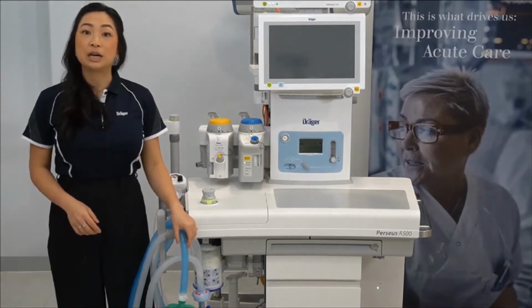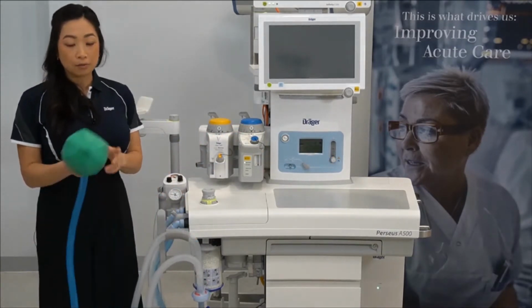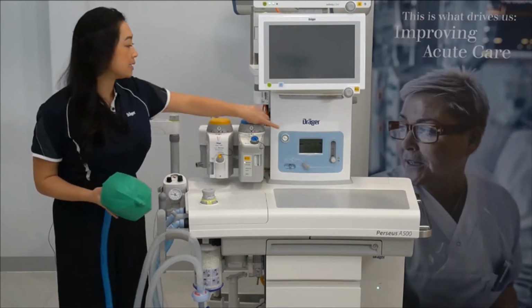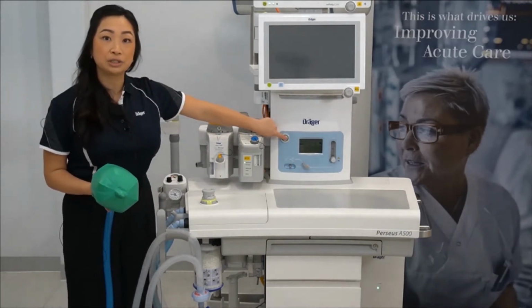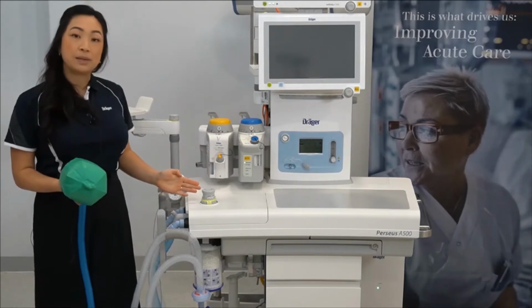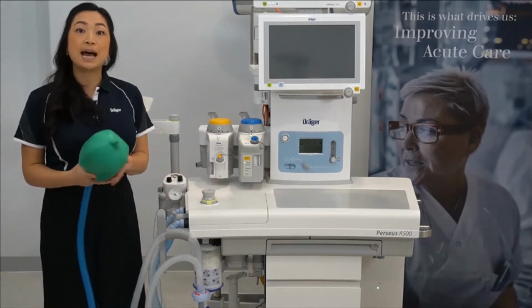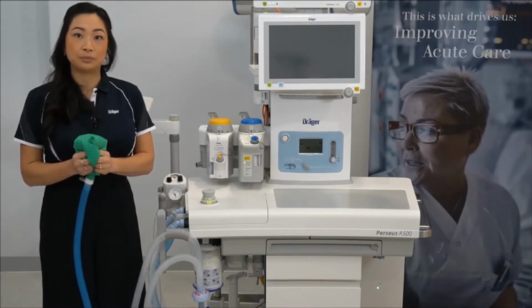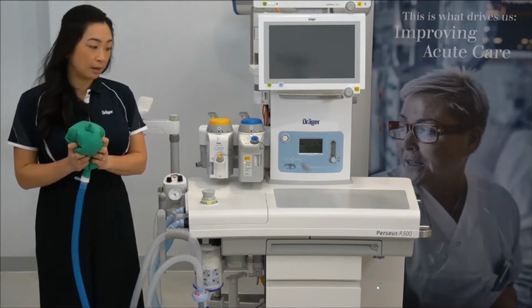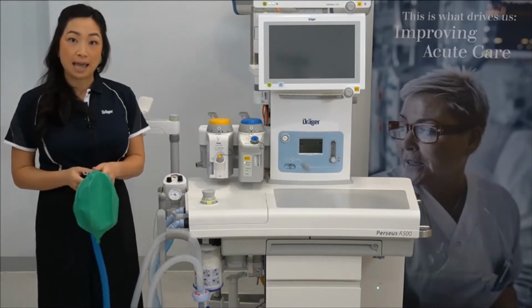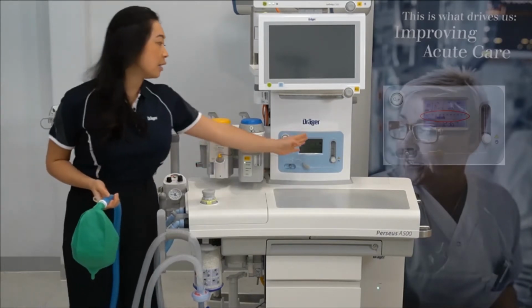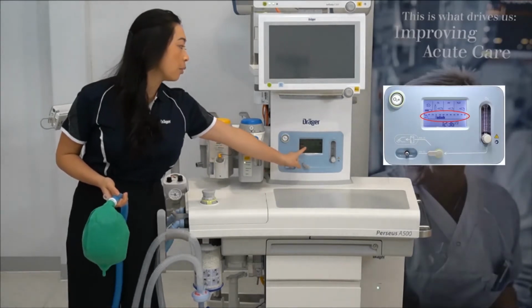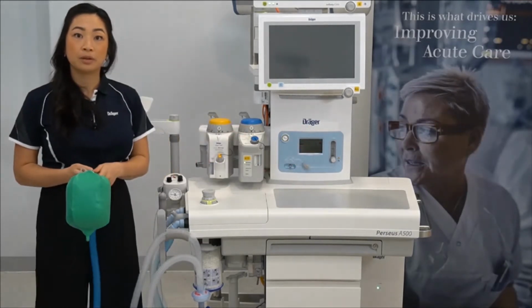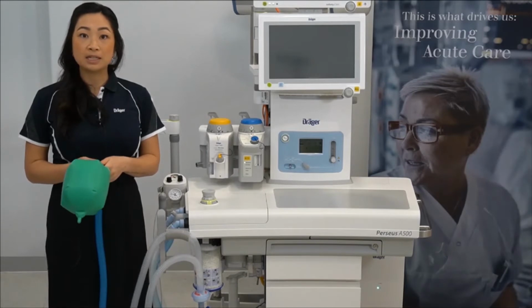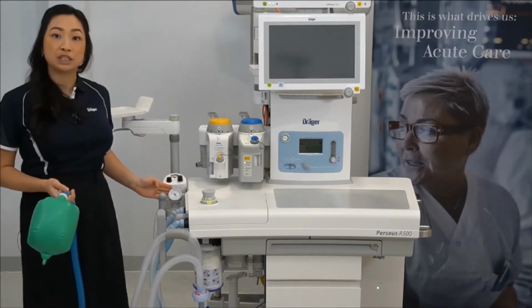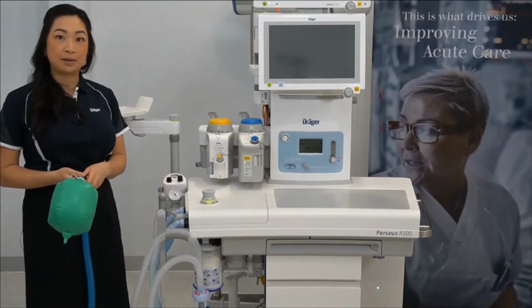Connect your patient up to the breathing circuit. Rapidly fill the breathing bag if necessary using the oxygen flush. Check your APL valve and start manually ventilating the patient. To verify your patient's airway pressures, this can be seen on the monitor screen on the airway pressure bar graph. For users that have their device configured with a manual pressure gauge, you can also check here.